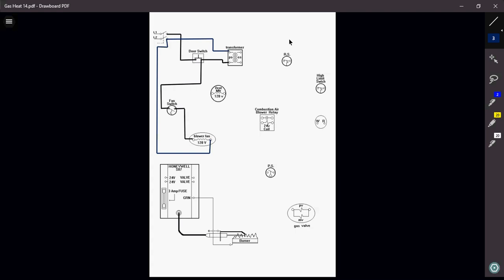Remember, source, path, switch, load. All right? For our transformer, we have our power source. Here's our source, our path, our switch, and the primary side of the transformer is our load, right? So for our blower, we actually have two switches in series with each other, if you kind of think about that. Here's our source, our path, our switch, right? Here's one switch. Here's our path again, right, which goes down to another switch, path, load, and then right back. So troubleshooting your equipment, you break it down just like I am explaining here how to wire it. You break it down into smaller groups. Once you're able to do that, your troubleshooting is going to be a lot easier to understand and make sense of what is actually going on.